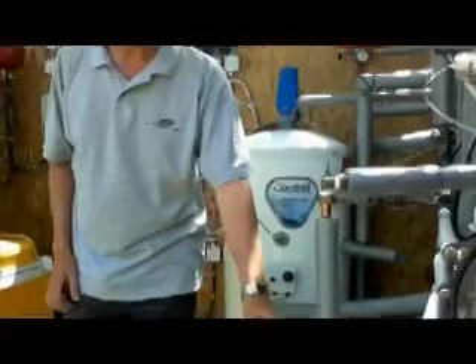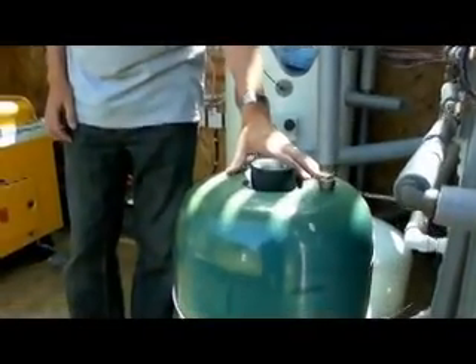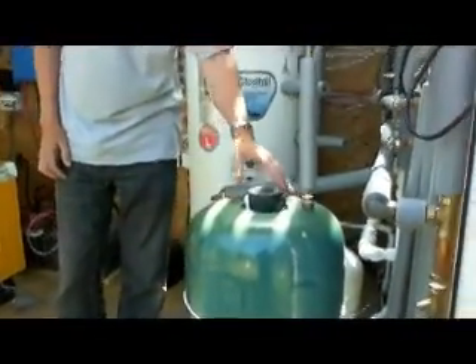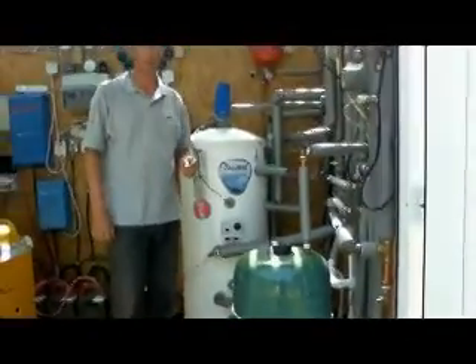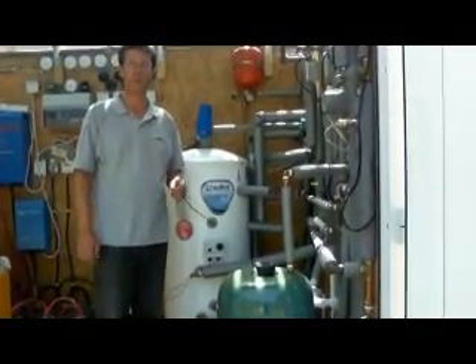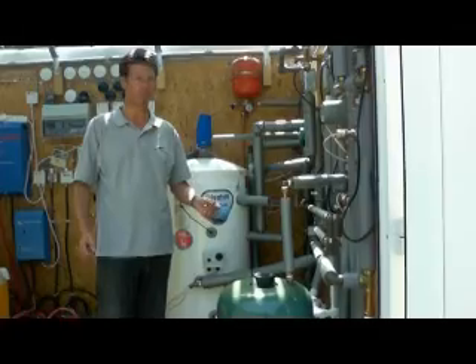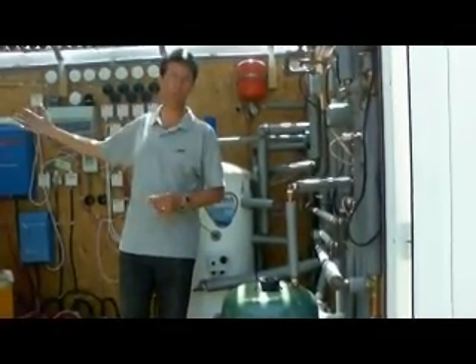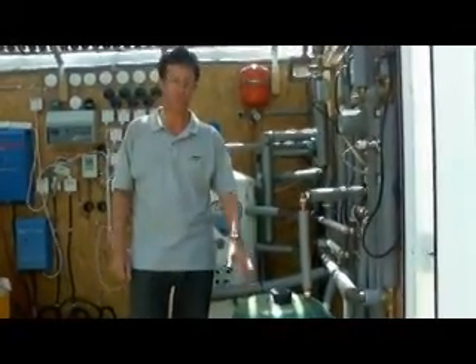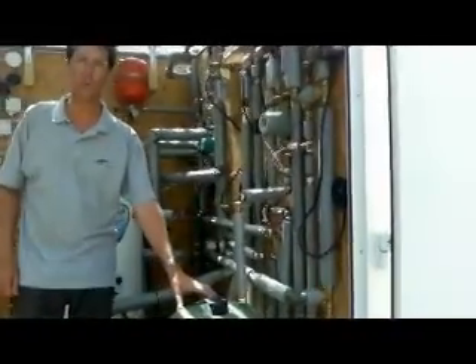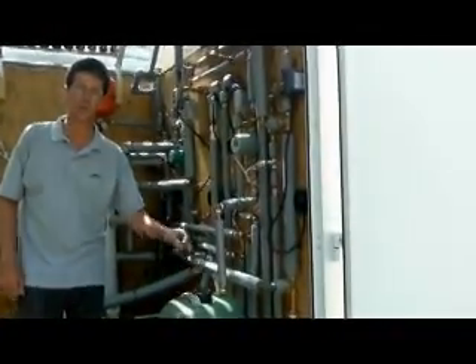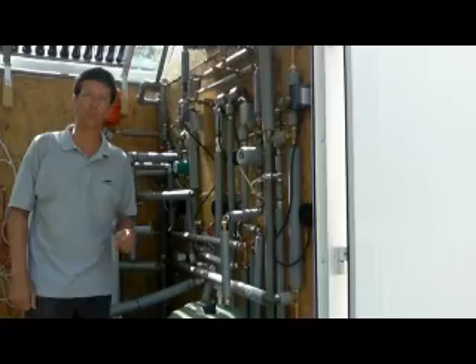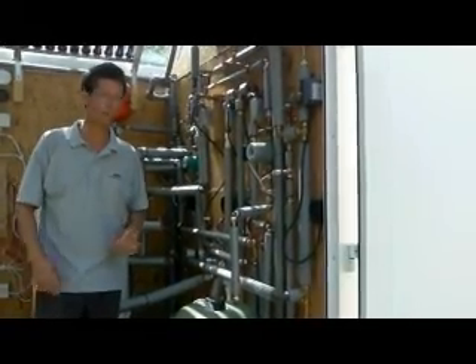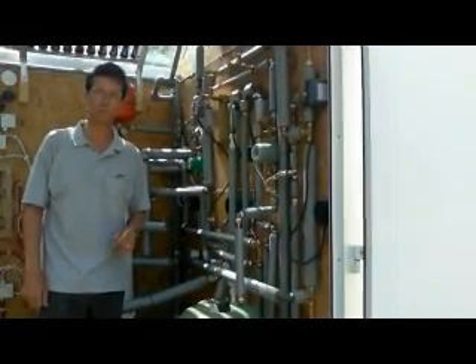This little tank is our comfort heating tank. So during those early spring and late summer days where it's a bit nippy outside and you don't want to turn the central heating on, the air source heat pump actually takes control of the central heating, heats the central heating water through this tank as a heat exchanger, and in the house we've got a lovely sort of background heat in our radiators. Boiler doesn't switch on at all.